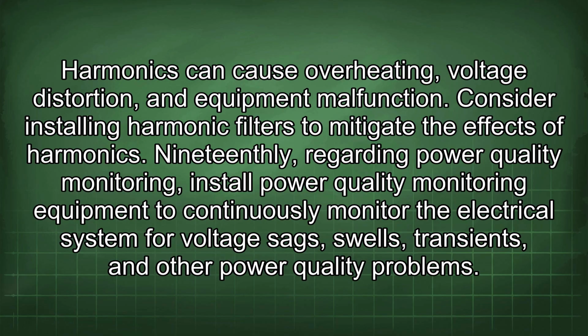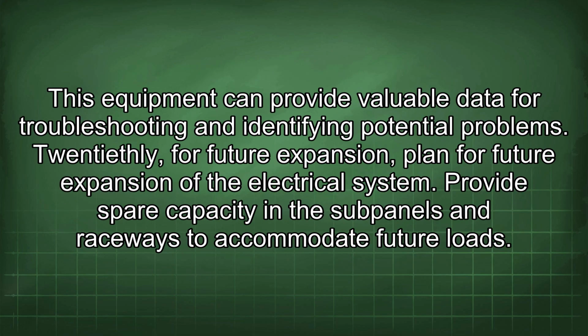Harmonics can cause overheating, voltage distortion, and equipment malfunction. Consider installing harmonic filters to mitigate the effects of harmonics. 19thly, regarding power quality monitoring, install power quality monitoring equipment to continuously monitor the electrical system for voltage sags, swells, transients, and other power quality problems. This equipment can provide valuable data for troubleshooting and identifying potential problems.